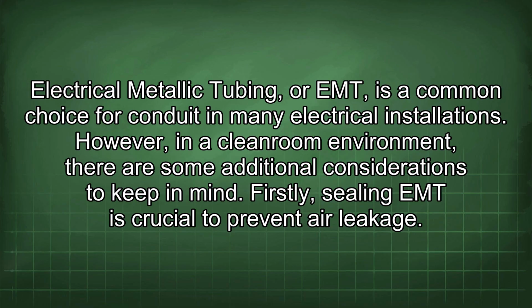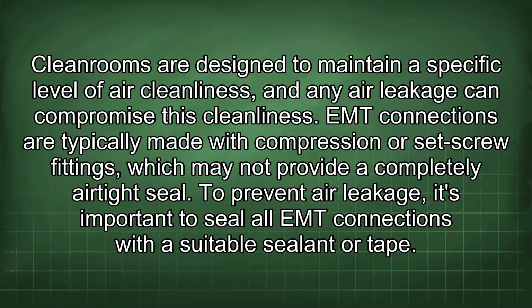Electrical metallic tubing, or EMT, is a common choice for conduit in many electrical installations. However, in a cleanroom environment, there are some additional considerations to keep in mind. Firstly, sealing EMT is crucial to prevent air leakage. Cleanrooms are designed to maintain a specific level of air cleanliness, and any air leakage can compromise this cleanliness. EMT connections are typically made with compression or set screw fittings, which may not provide a completely airtight seal. To prevent air leakage, it's important to seal all EMT connections with a suitable sealant or tape.